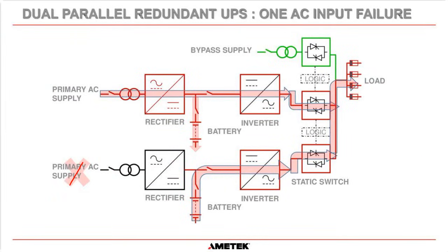Now, if the primary AC supply fails for UPS B, then UPS B will go onto battery. This is specific to an AMETEK SCI parallel redundant system. Some of the other manufacturers might handle it slightly differently. But what we do is UPS B goes onto battery, and the inverter carries on going as normal. Once again, this one will supply 5 kVA, and this one will supply 5 kVA, if we use the same rating as before.